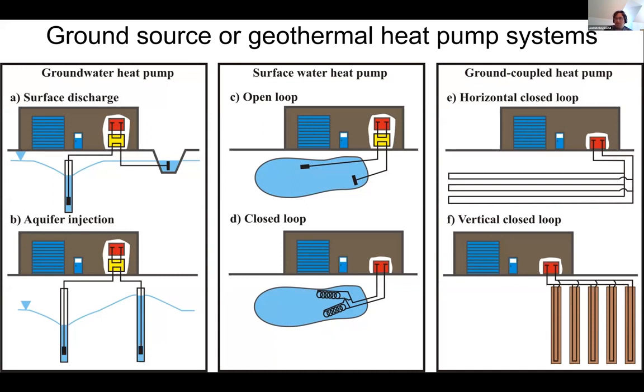However, in Canada, they are the type of system that is most popular. I think 80% of systems are closed loop. And it's because they're pretty much a plug and play solution, right? Since it's a low risk option and you can install this anywhere, right? You don't need a permeable aquifer. You just need enough space to dig a trench and install your pipe, or if not, drill some boreholes and install in the ground. Well, they tend to be more popular, although the payback period can be a bit longer.